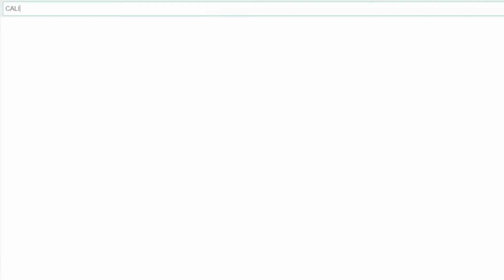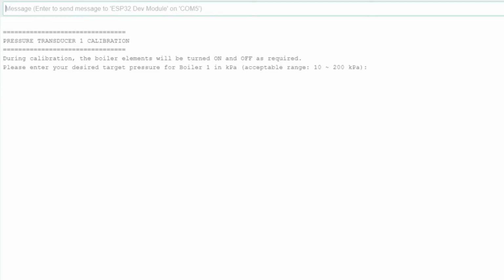The next sensor that requires calibration is the pressure transducer. To start the calibration wizard, I'll send the command calibrate PT1. During calibration, the wizard will take control of the boiler element relays. First, I'm prompted to enter my target pressure for boiler 1. For my machine, the value is 110 kPa.